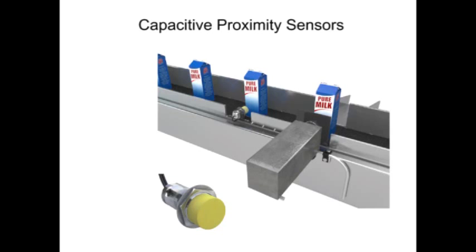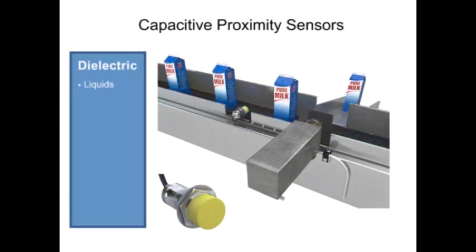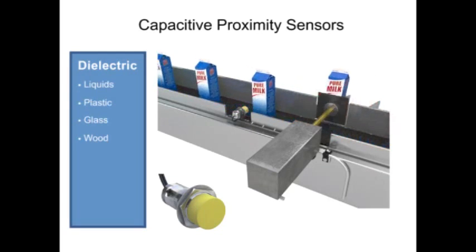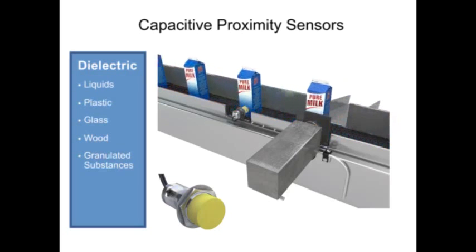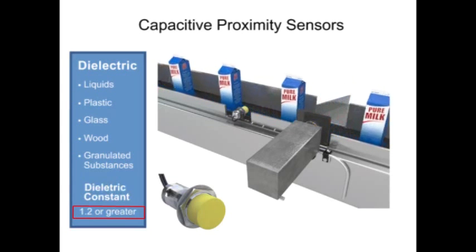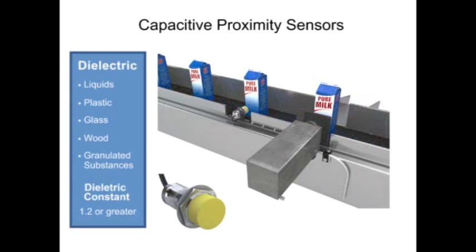Capacitive proximity sensors, on the other hand, can detect dielectric materials such as liquids, plastic, glass, wood, and granulated substances, as long as the material has a dielectric constant of 1.2 or more. Their range is from 3mm to 15mm depending on the dielectric material to be detected.